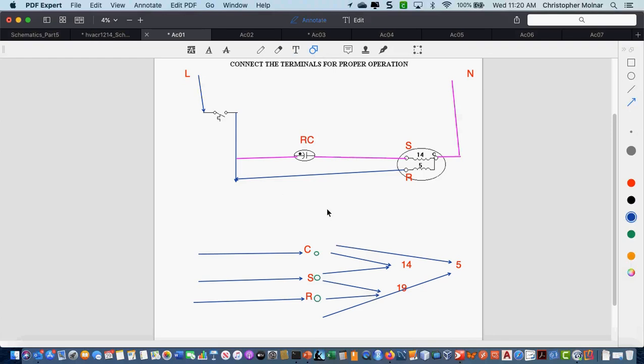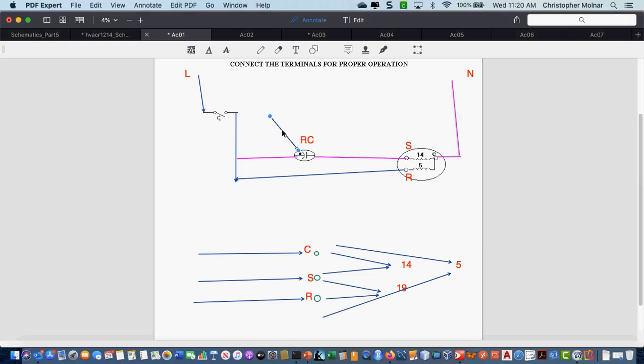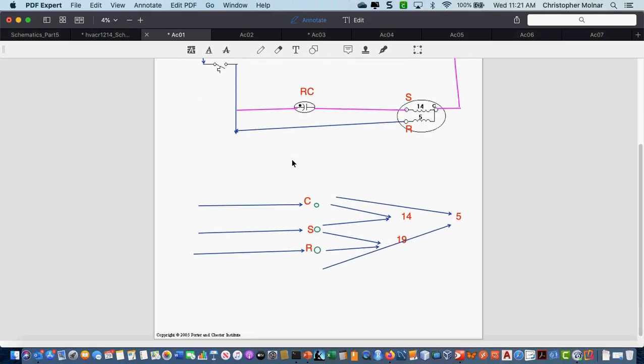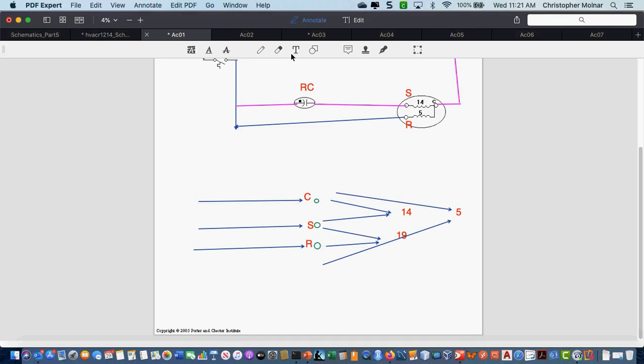However, word of warning, more and more diagrams I'm seeing do not have that dot. We don't see it often in the newer equipment, because everybody working on the equipment should know that if I do not have any switching device, if this is a straight run through the capacitor from line to start, we know it's a run capacitor. We also know when we're working on equipment that run capacitors are metal. So run capacitors are left in the circuit when the circuit is powered.